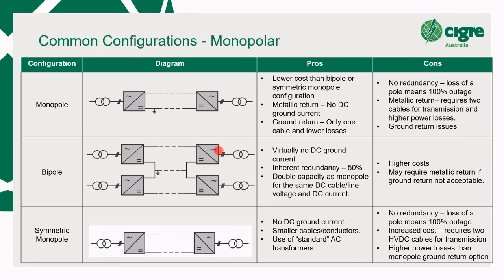Bipole. So the bipole looks like this. It's two asymmetric monopoles connected. It has two converters instead of one. If this bipole and this monopole had the same megawatt capacity, each converter here would be 50% of the overall power. It has an inherent redundancy. So if you get a fault in, say, this high voltage cable, then you could have some switching in here that will allow you to operate in monopole mode for a while. Of course, the same question comes about: do you have a metallic return or do you have a ground return during that period? But it can provide this 50% capacity.